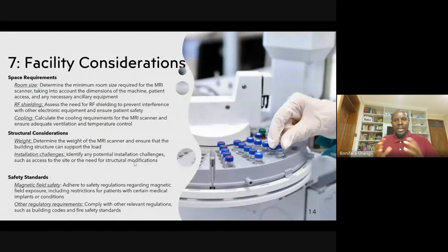Then an MRI machine is not just about the equipment. A lot of times there are a lot of ancillary assets that come with the MRI machine. So first, you need a considerable room size. Then, since an MRI produces magnetic radiation, you need to do RF shielding to prevent that magnetism from interfering with other things around the area or electronic communication.